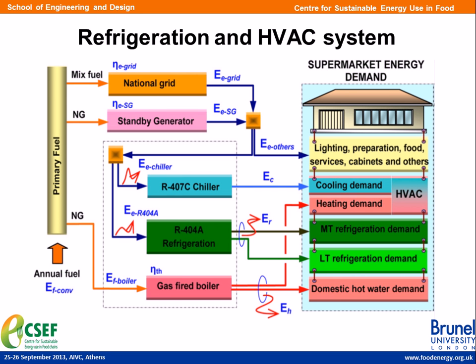Now, as we said, refrigeration is quite a high component and quite core to the function of the supermarket, but refrigeration interacts quite a lot with the HVAC system. In this slide, we have the supermarket energy demand, which includes the building, lighting, food preparation, services, cabinets, and others, with a cooling demand and a heating demand. We have the medium temperature and low temperature refrigeration cabinets, and also domestic hot water demand. Usually in the supermarket, these are provided through electricity from the national grid and a standby generator, and this electricity gives the energy to the chiller and the refrigeration that feed the different demands. In the UK, heating is usually done by gas, so we have gas-fired boilers that provide the heating demand and domestic hot water.